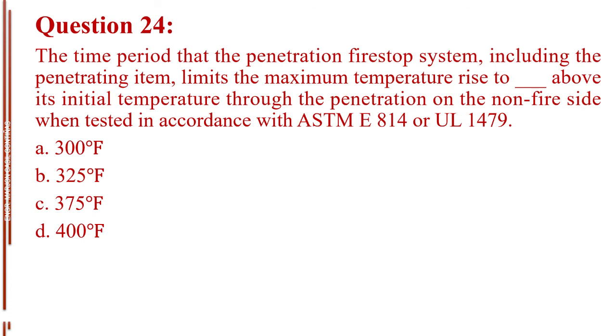Question number 24. The time period that the penetration fire stop system, including the penetrating item, limits the maximum temperature rise to blank above its initial temperature through the penetration on the non-fire side when tested in accordance with ASTM E 814 or UL 1479. A. 300 degrees Fahrenheit. B. 325 degrees Fahrenheit. C. 375 degrees Fahrenheit. D. 400 degrees Fahrenheit. The answer is Letter B, 325 degrees Fahrenheit.